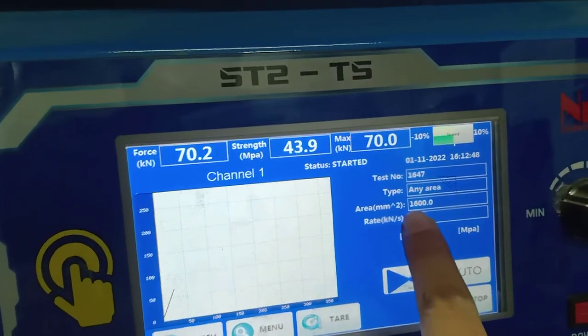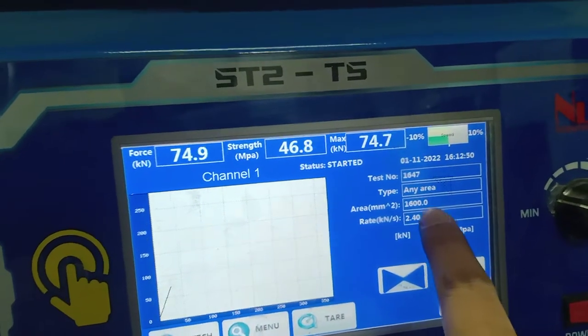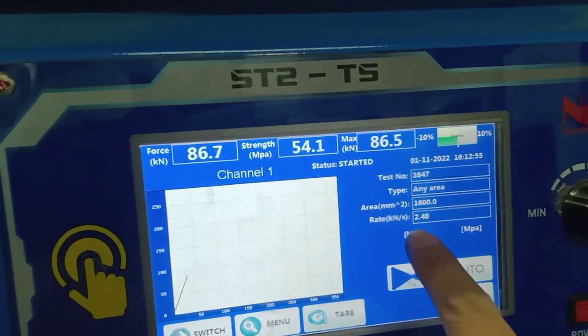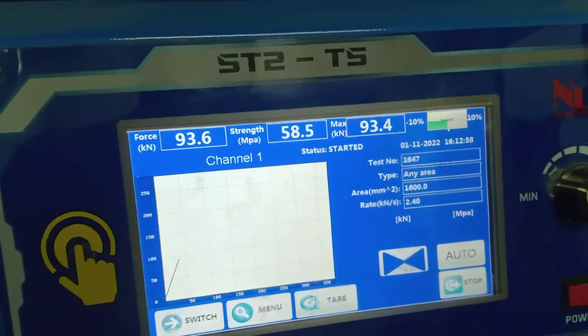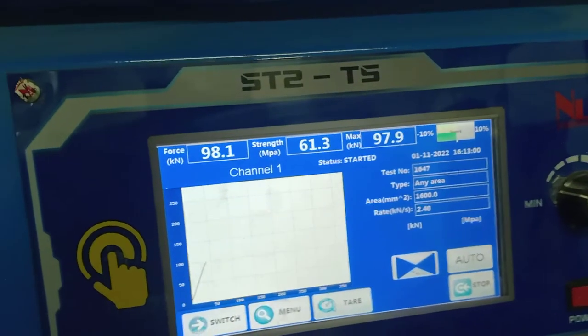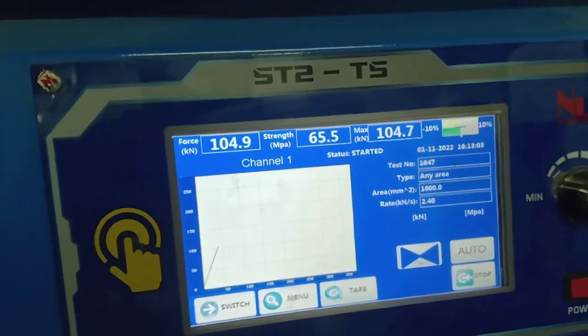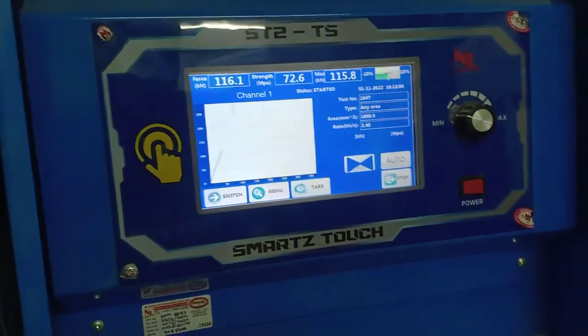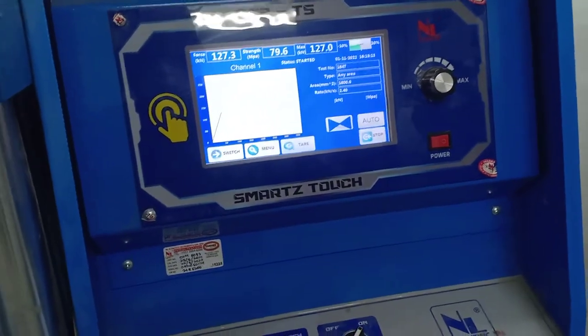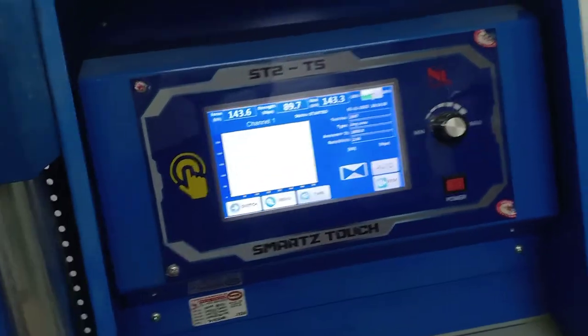The sample area surface is 1600 square millimeters. The rate is 2.4 — this is called the stress rate. According to the standard, the stress rate should be 2400 newtons per second, or 2.40 kilonewtons per second. My fellow researchers and students, I think this video should be helpful — follow the instructions properly and read the standard before using the machine.